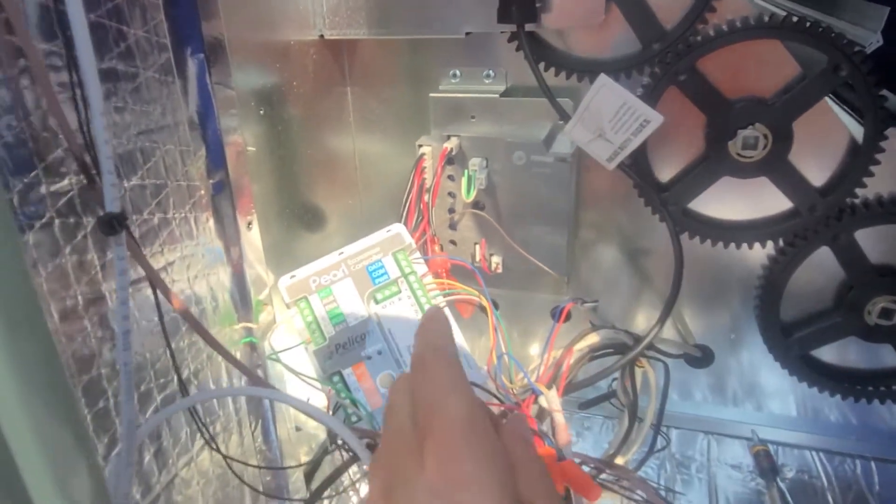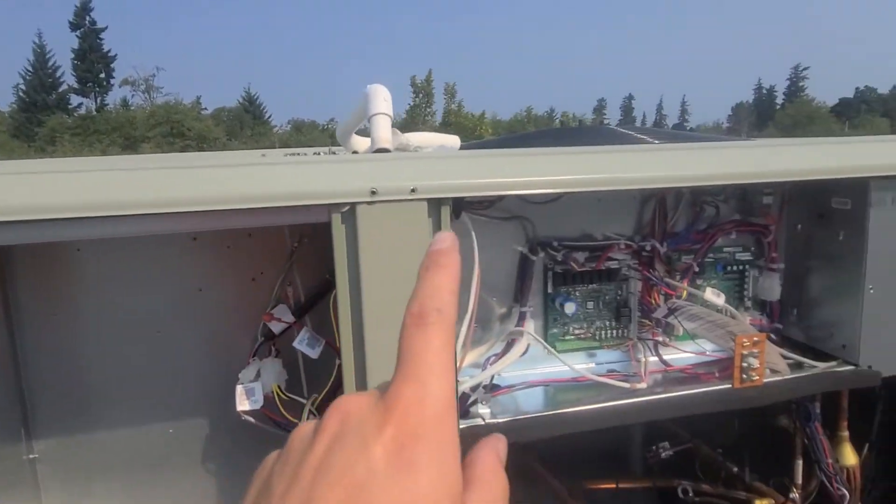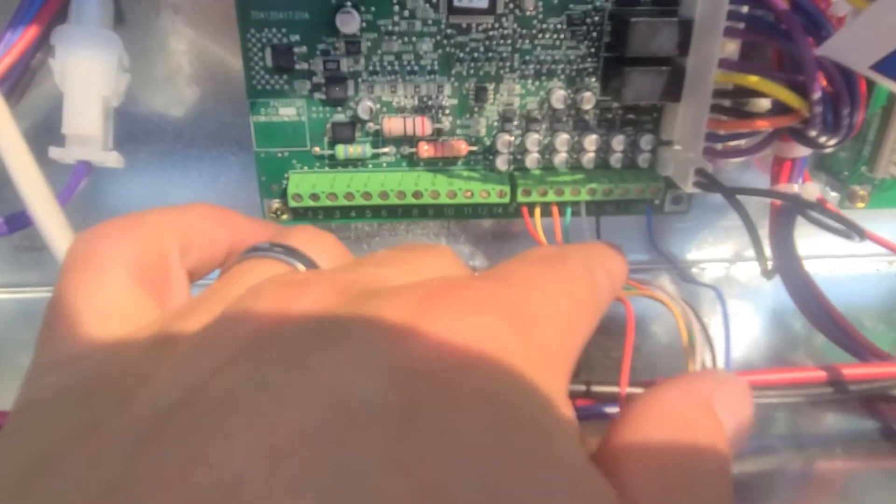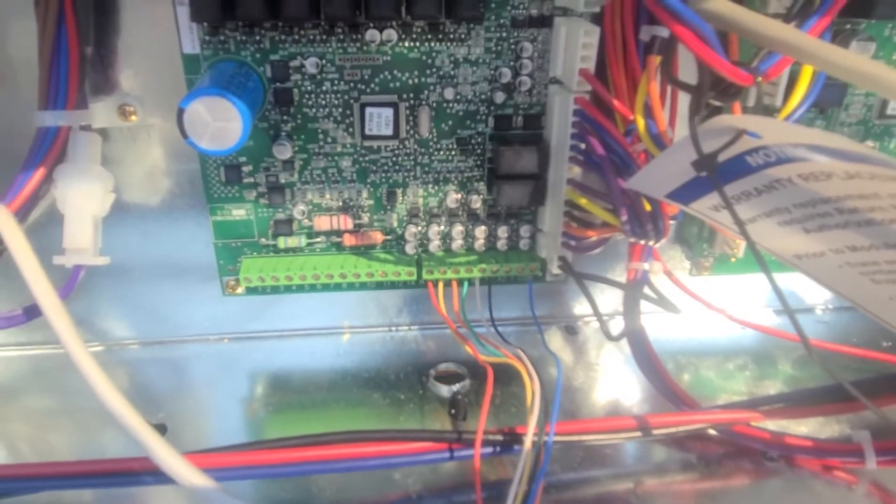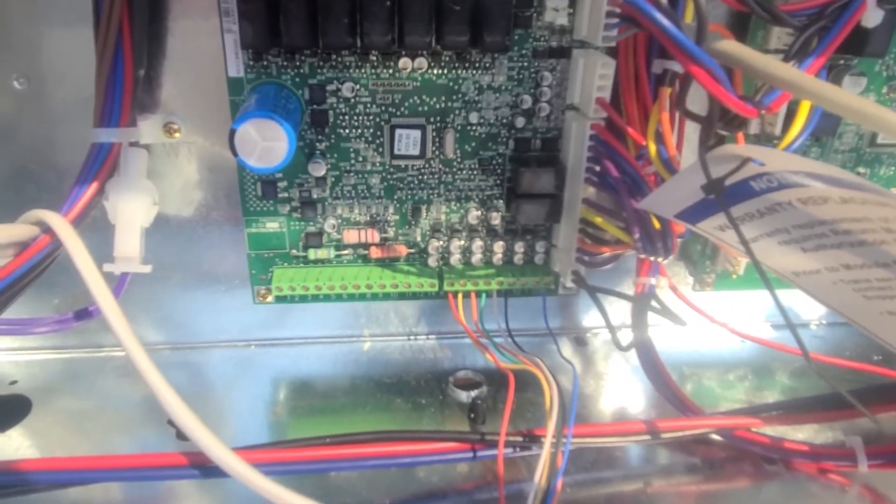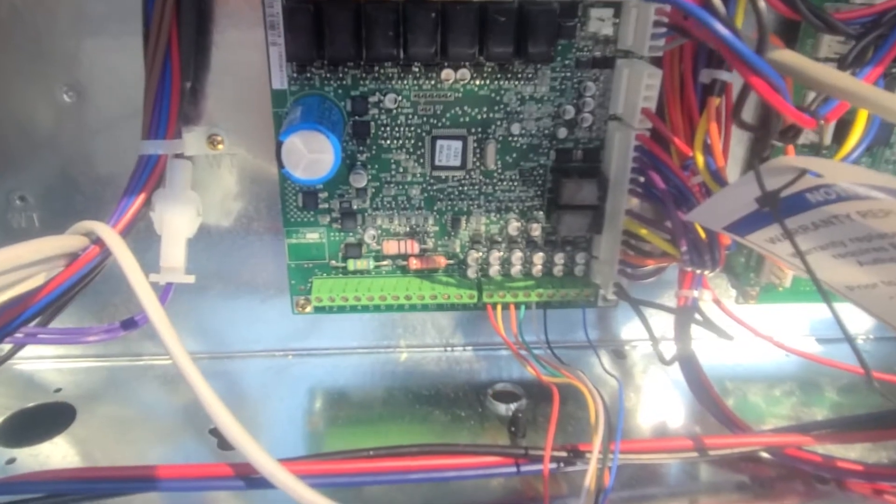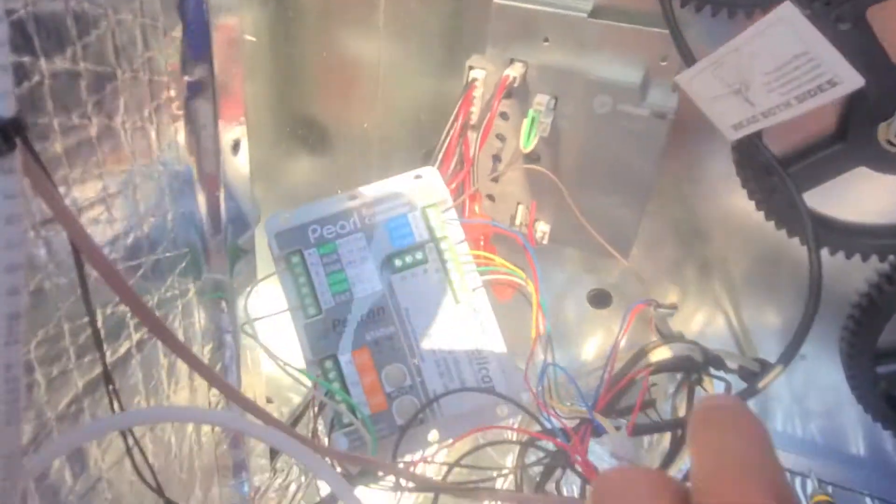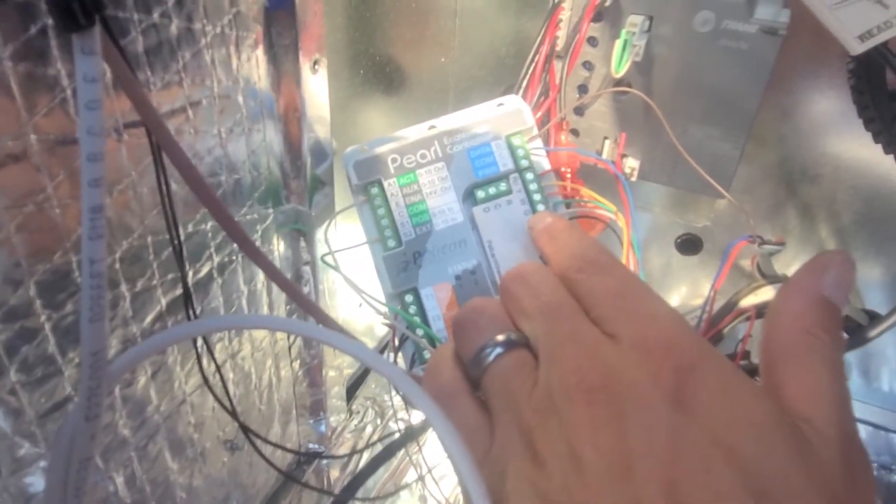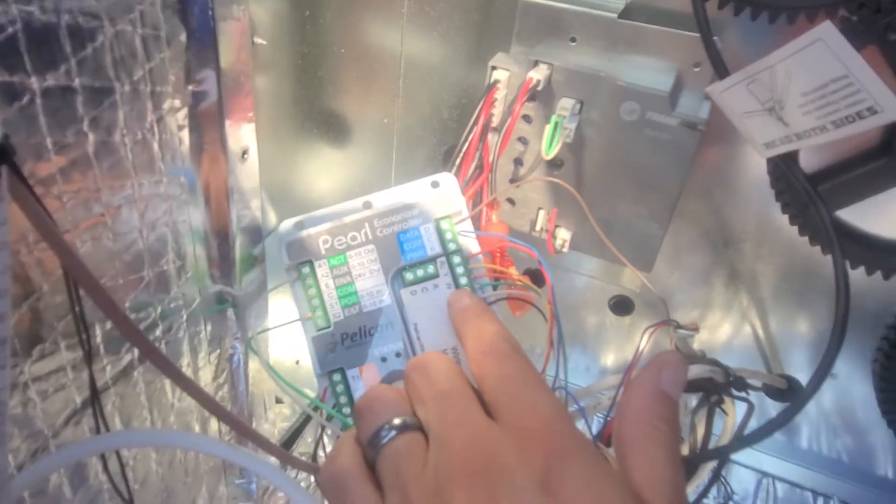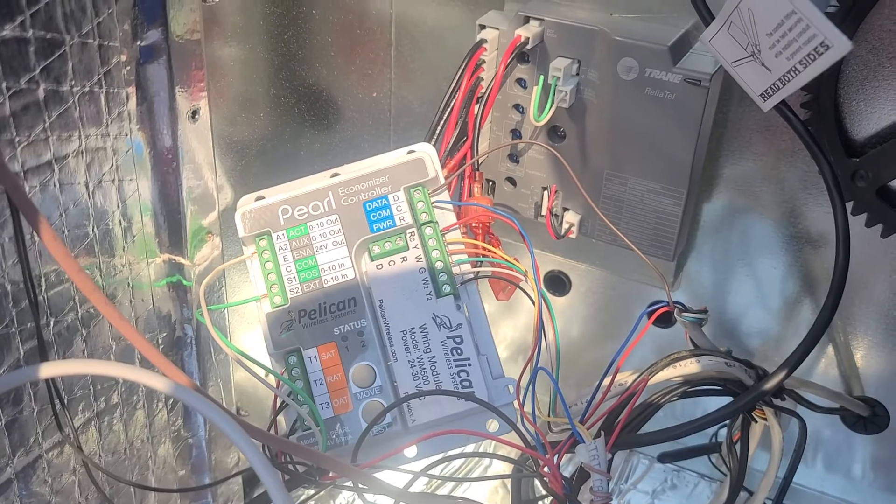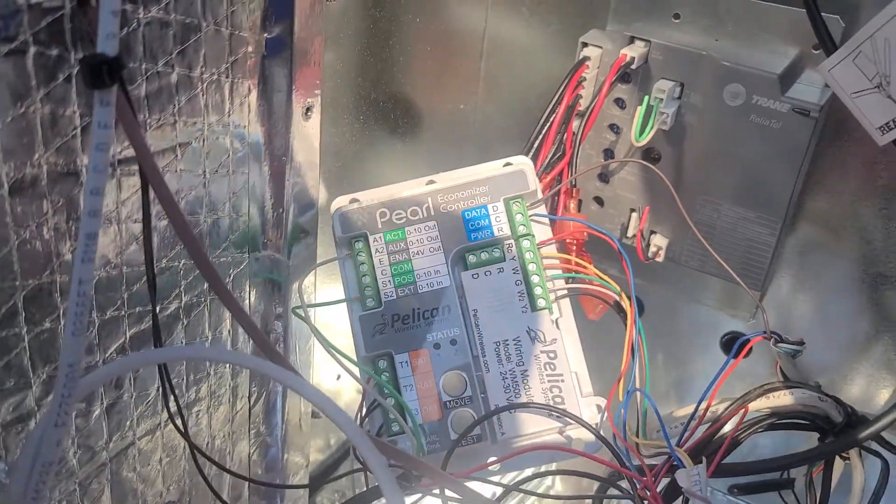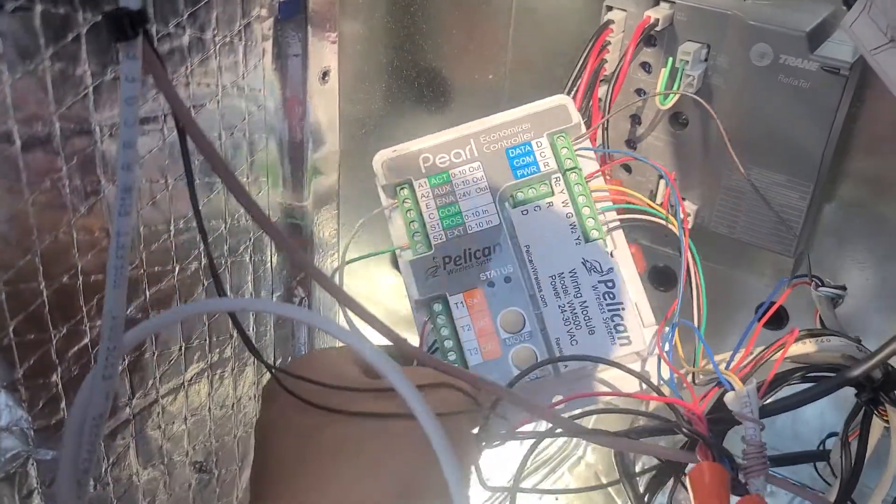From this module you will wire up your normal RC, W, G, W2, Y, Y2. I just ran it up across the top and then dropped it in here. It's pretty standard. The book shows you really well where you need to land everything: power, Y, reversing valve, fan, W2 which is actually my strip heat, then Y2 and common. One thing that's different on this: it doesn't give you an actual O or B terminal for reversing valve, so you actually land it on the W.